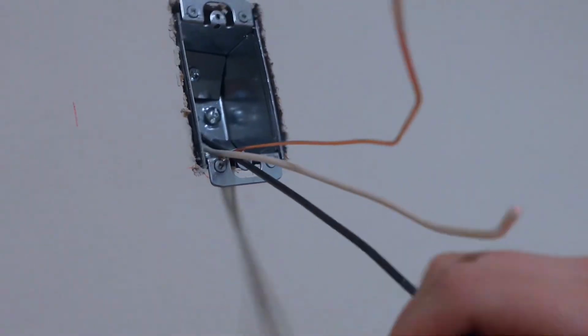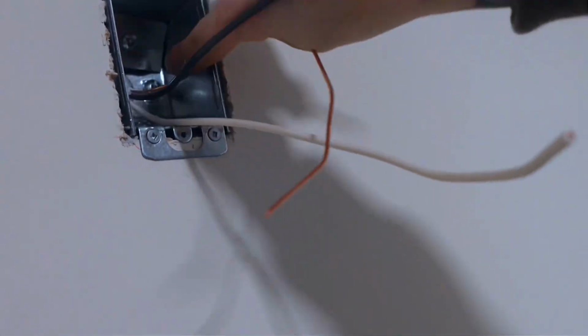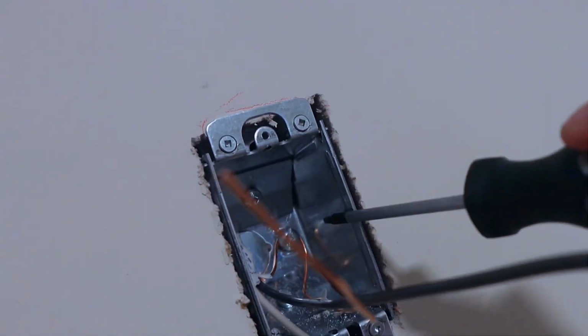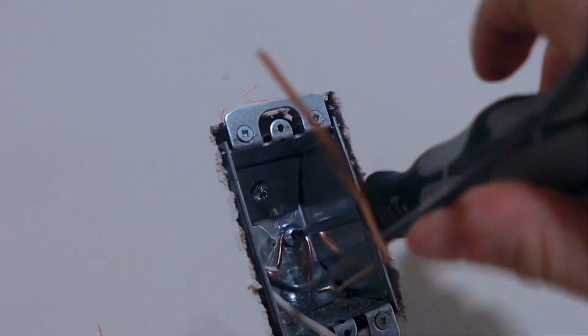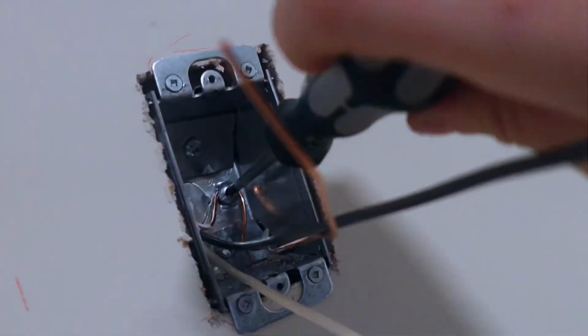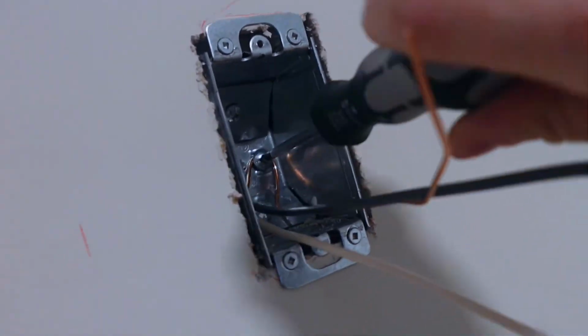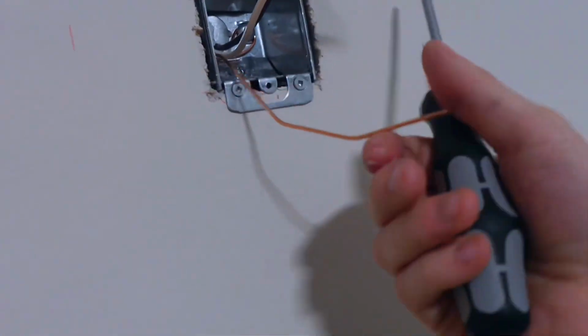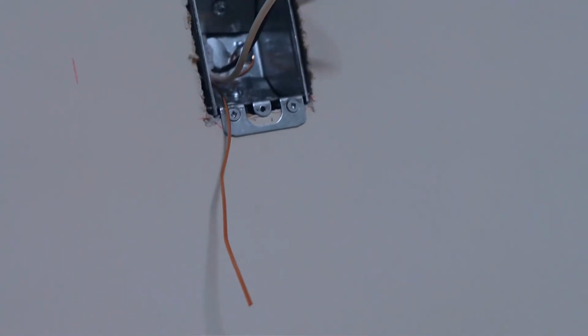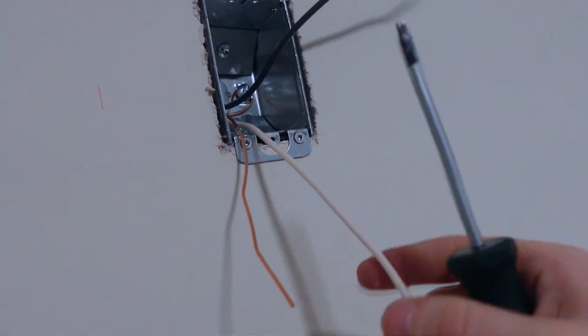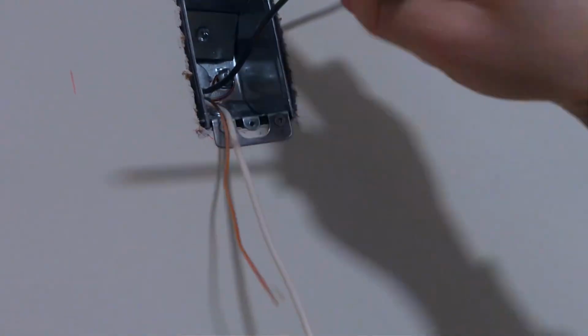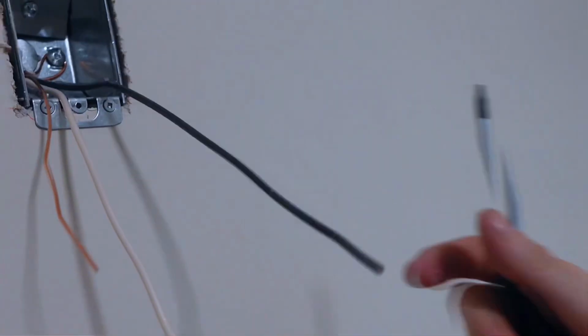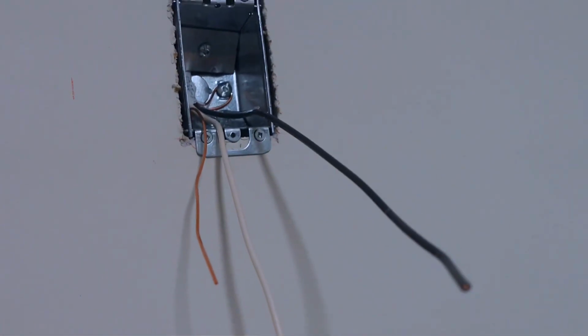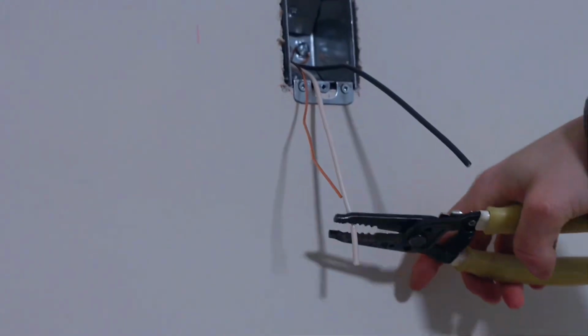Because this is a metal box, it's not a plastic box, we do have to bond the box, and you're going to wrap the bond wire in the direction that the screw tightens. So as you are tightening, it will wrap it around the screw further instead of doing the opposite. We're going to place this bond wire onto the left side of our box because that's where the bond screw is on the receptacle. Our neutral on that side and our hot is on this side. So let's strip these wires and put the receptacle on.